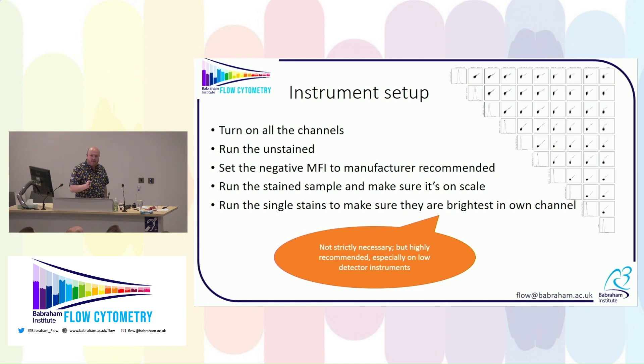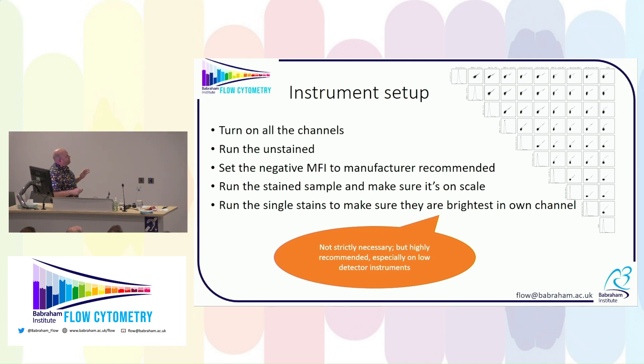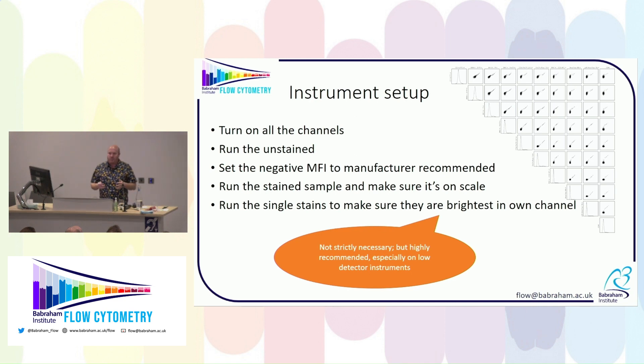If you want to do this yourself, it's really simple. Turn on all the channels. Run your unstained control and set a baseline setting — on the BD machines I love using the application setting worksheet to set the baselines. Put it to the negative region, whatever the manufacturer recommendation is. Run the stained sample and make sure everything is on scale. On full spectrum flow cytometry, if things go off scale it's a disaster — never let anything go off scale.